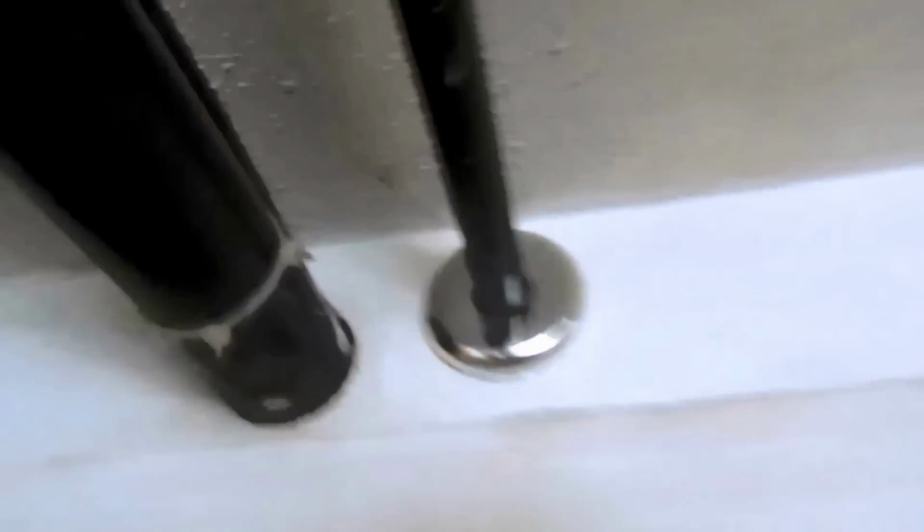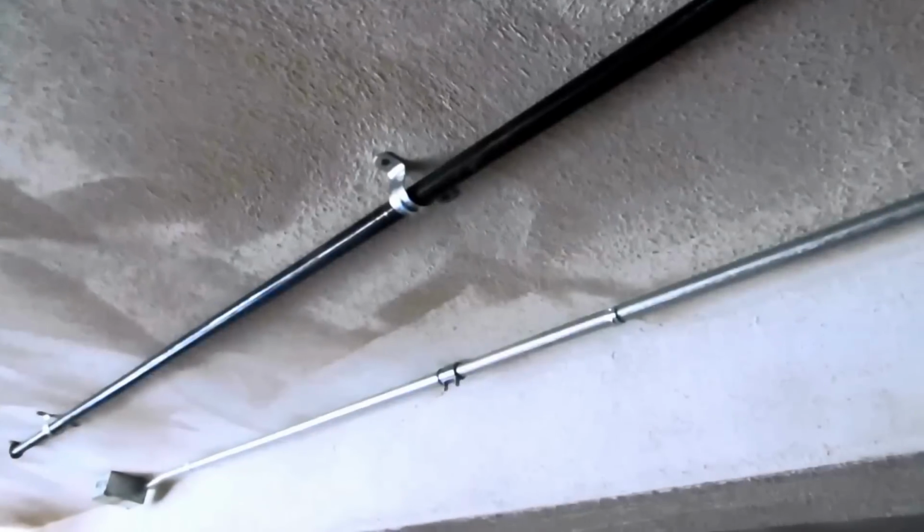Scutcheon for that looks better. Going through the wall. Boom. It comes over. A couple hangers and going up. It's actually pitching back. So any liquid in the gas line, it'll drain back to the T.